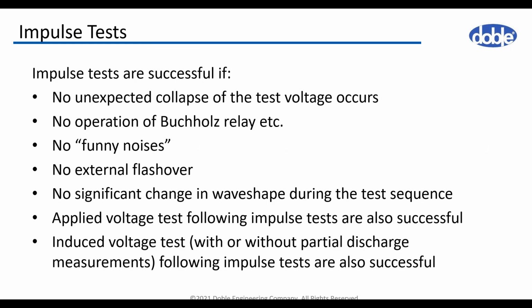The criteria for successful testing include absence of sudden collapse of the test voltage, or no significant difference between the voltage and current impulses recorded at reference and full test voltage. Operation of protective devices like Buchholz relay or strange noises are also an indication of a fault, and sometimes failure may not be detected based on the transient oscillogram, and success of the impulse test is thus confirmed through the applied voltage and induced voltage tests, which follow the impulse testing.